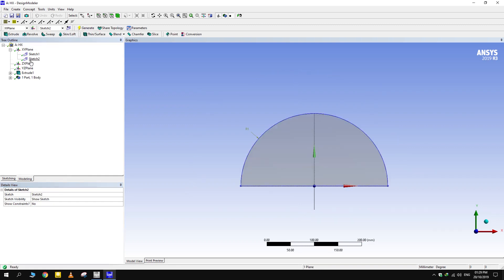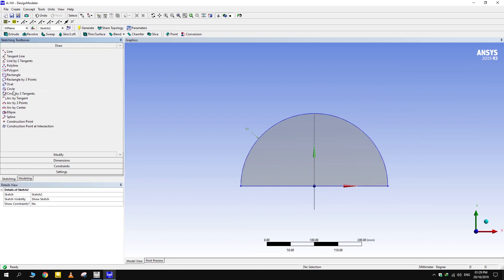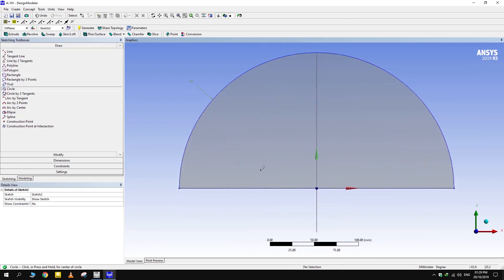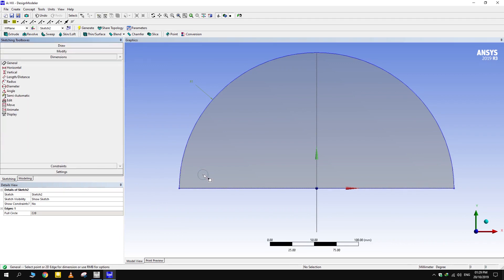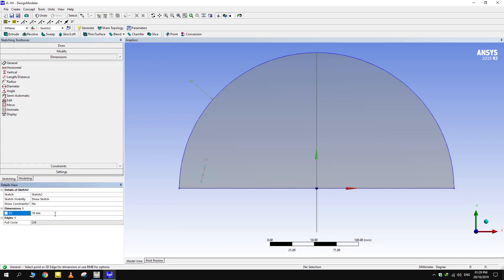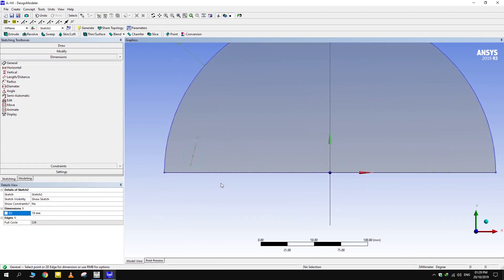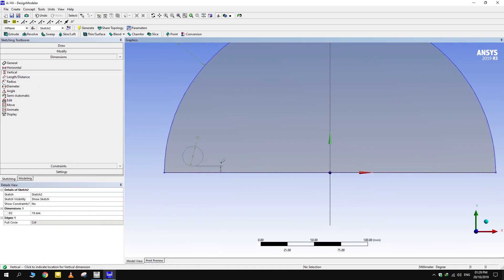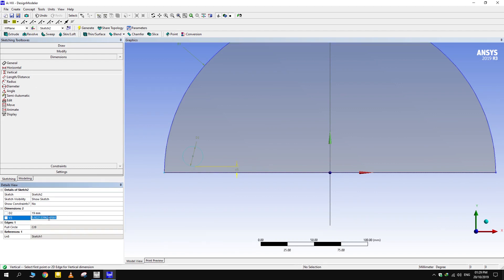Draw another sketch. Then draw a single tube the similar way. Tubes have 19 mm diameter. The tube can be kept at any distance from the walls depending on the design. But we will keep the clearance equal to that of between the tubes. Triangular pitch of tubes is 23.8 mm, which gives tube to tube clearance of 4.8.